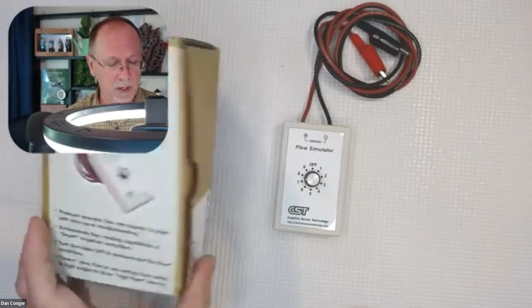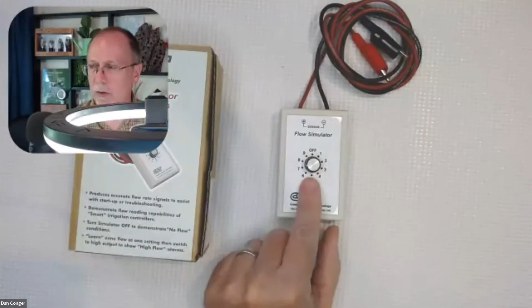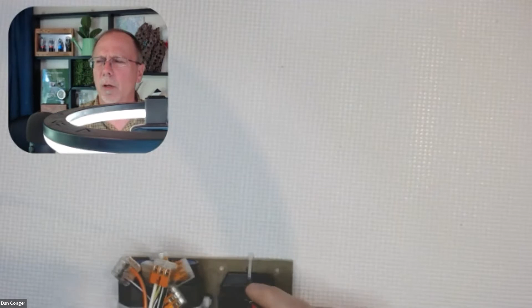So here's one that's completely different, and I didn't even know it existed. This is made by CST, and there's probably some others on the market. This is a flow simulator. Let's see what's inside of it. It has a dial in here that's pretty simple. It's just got multiple settings, and it's going to clip onto there. Then it has a chart of information on what number you might want to use to illustrate various flows. So if I wanted to simulate 1500 GPM, I'd set it to setting 9.